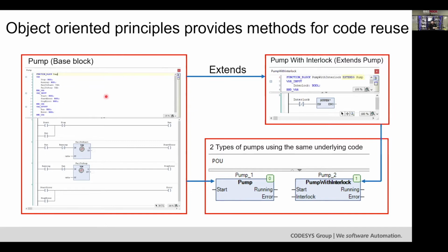But then you have the ability to extend that logic. What that means is you're taking that underlying code and extending it with this one block here, saying extend pump. So that's extending this code, and you're calling that code with this single block that says super. What that ends up meaning is I now have all the functionality of the base pump in this block, and I just added a single interlock. So just by adding one instruction, I now have two types of pumps: my base pump, and a pump with an interlock.